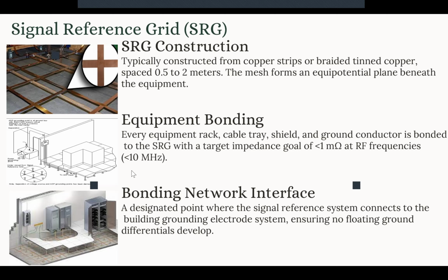And when we talk about radio frequencies, the target impedance is less than 1 milliohm. The designated point where the signal reference system connects to the building ground is very important. We have to make sure that we don't have any floating ground on that bonding point.